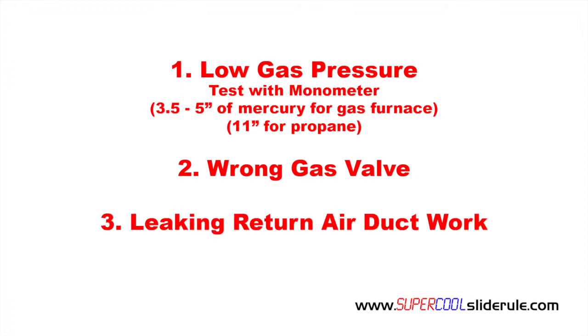Another cause is leaking return air ductwork. Carefully inspect the return air ductwork for leaks. Also use a type K temperature probe to verify the return air temperature is the same when it reaches the unit as it is at the return air grill.